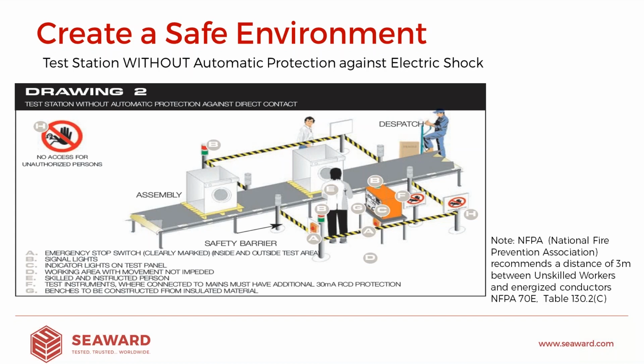One note for those of you in America, the NFPA, the National Fire Protection Association, recommend a distance of 3 meters between any kind of unskilled workers and any energized conductors. So for reference, you can look up NFPA 70E, and that's table 130.2. So effectively, we would need to ensure that our barrier system is 3 meters away from, in this case, the washing machine under test.